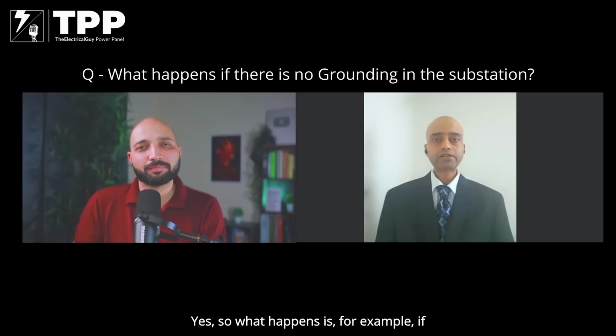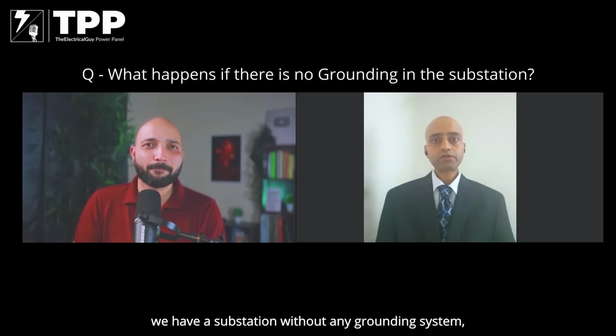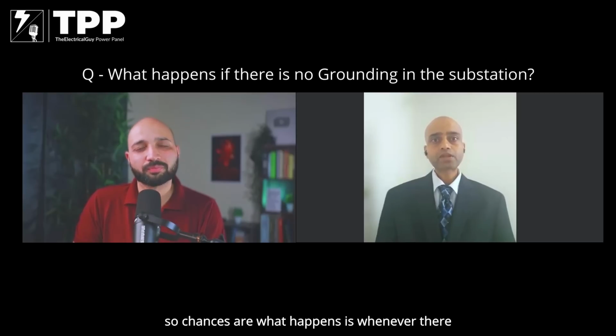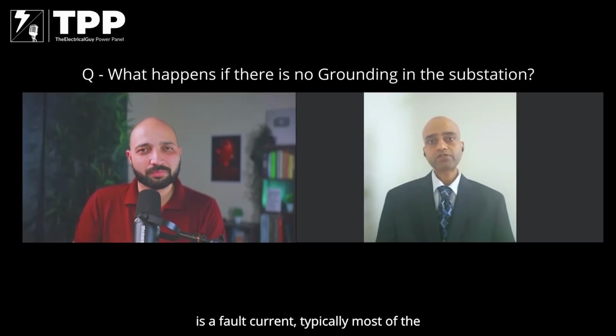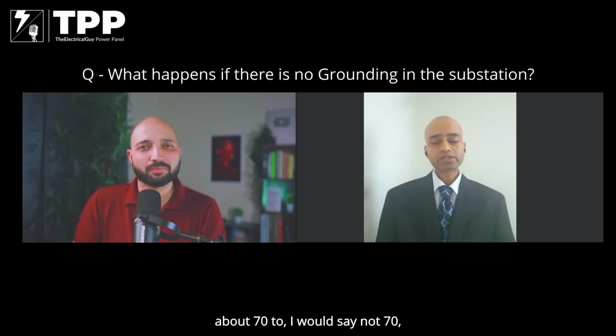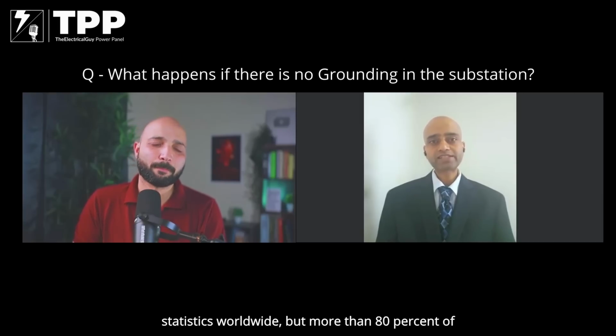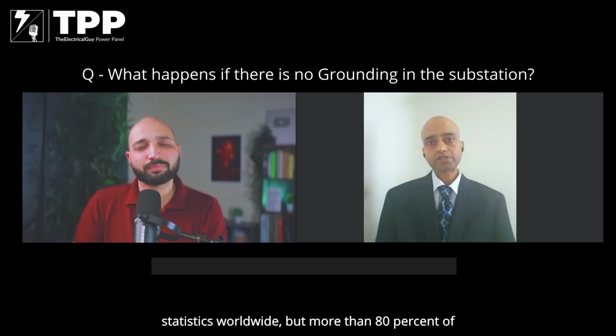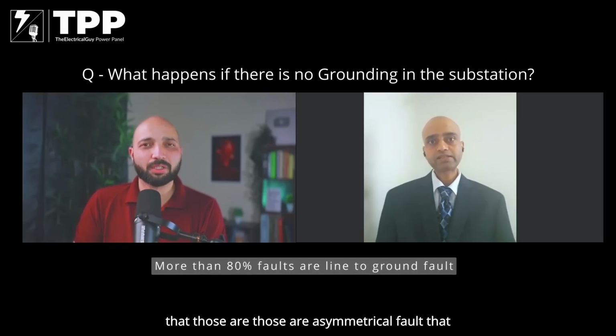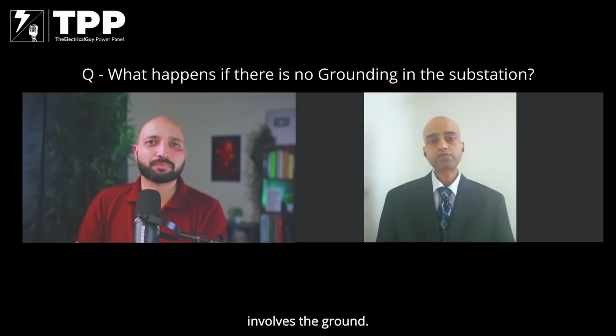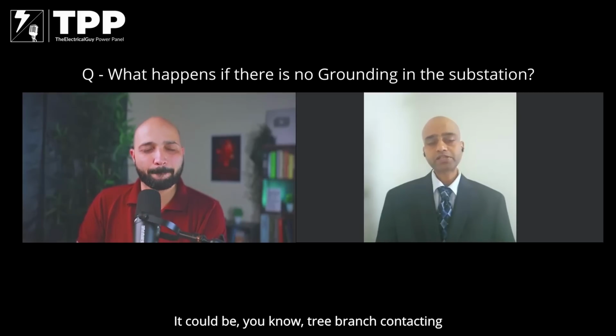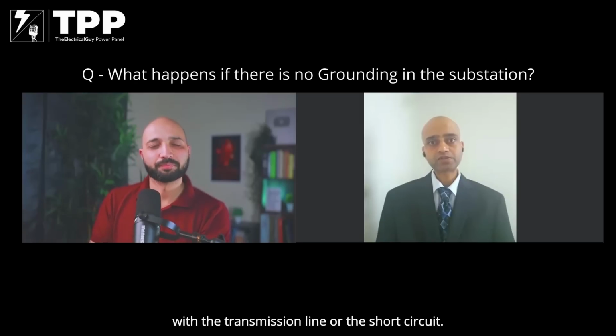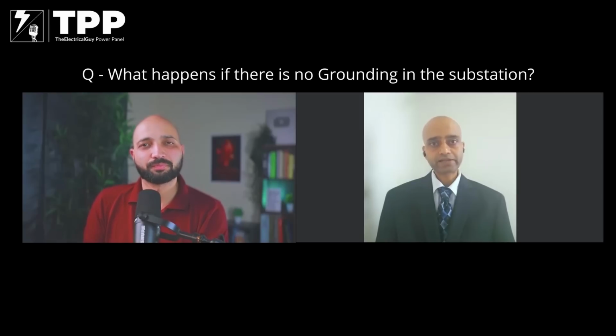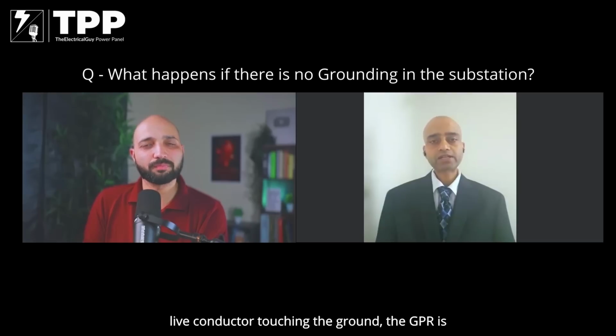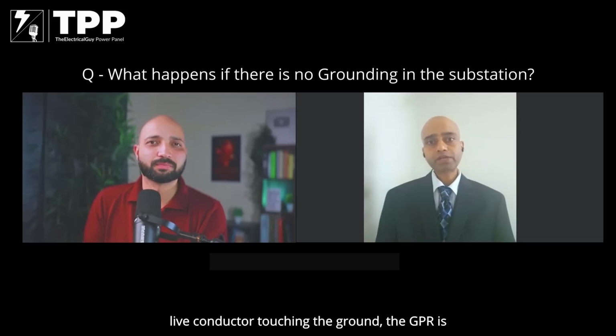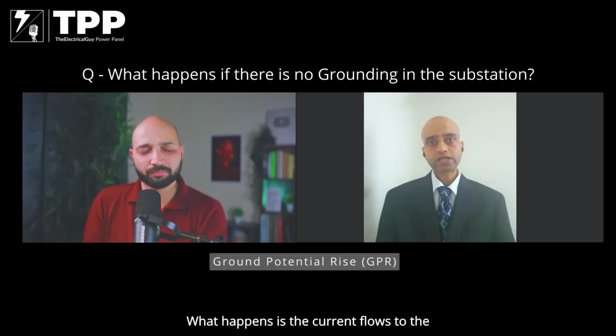Yes. So for example, if we have a substation without any grounding system, whenever there's a fault current, typically most of the, about 70 to, I would say not 70, but closer to, I don't know the statistics worldwide, but more than 80% of the faults are line to ground faults, meaning those are asymmetrical faults that involve the ground. It could be a tree branch contacting the transmission line, or a short circuit. That could be anything. Whenever there is a live conductor touching the ground, the GPR, called the ground potential rise, occurs. The current flows to the ground.